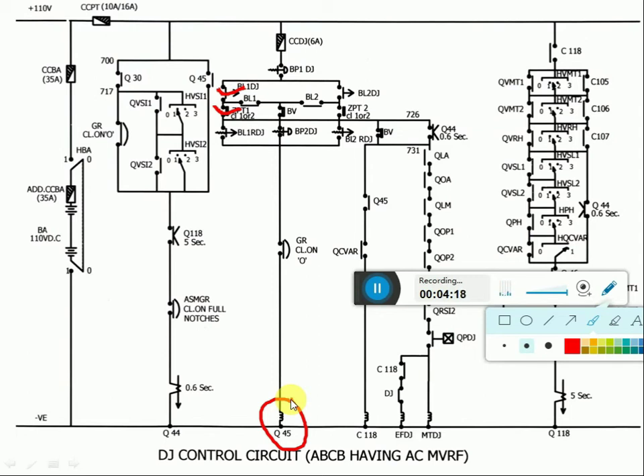If DJ holds, work further by manually operating Q45 whenever DJ trips. If manual operation is also not successful, meaning after releasing the Q45 pallet DJ is tripping, the trouble is not in the Q45 branch or Q45 coil. There may be other branches defective, like C118, EFDJ or FDJ. This is the troubleshooting for Q45 not pickup.